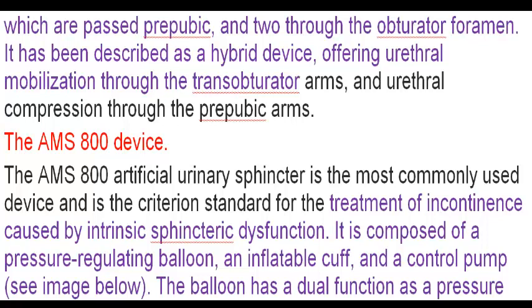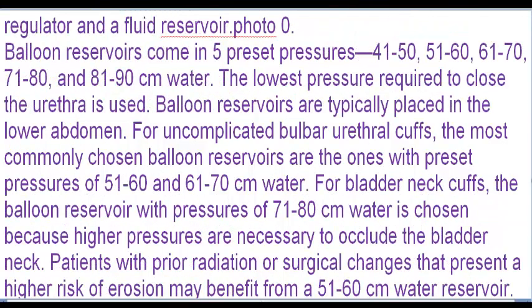The AMS 800 device. The AMS 800 artificial urinary sphincter is the most commonly used device and is the criterion standard for the treatment of incontinence caused by intrinsic sphincteric dysfunction. It is composed of a pressure-regulating balloon, an inflatable cuff, and a control pump, see image below. The balloon has a dual function as a pressure regulator and a fluid reservoir. Balloon reservoirs come in 5 preset pressures: 41-50, 51-60, 61-70, 71-80, and 81-90 cm water. The lowest pressure required to close the urethra is used. Balloon reservoirs are typically placed in the lower abdomen.